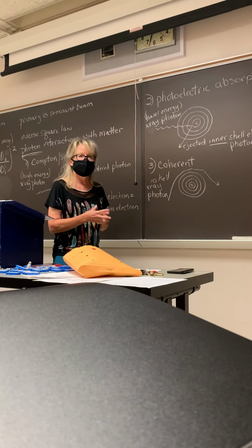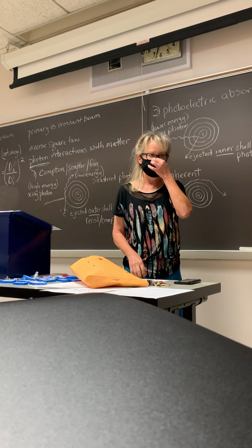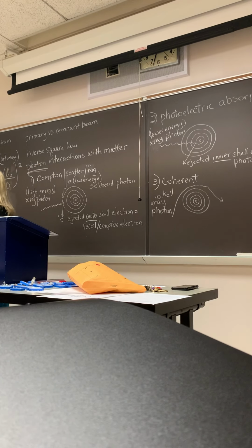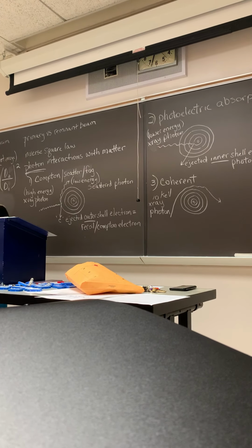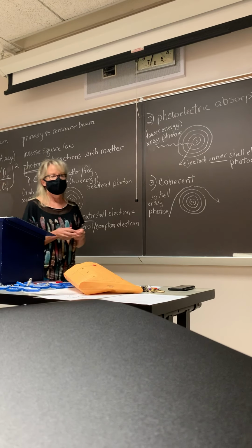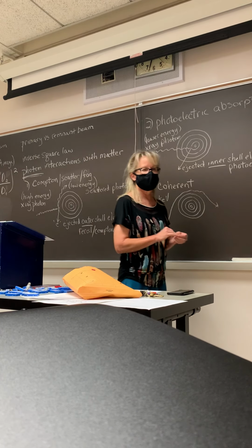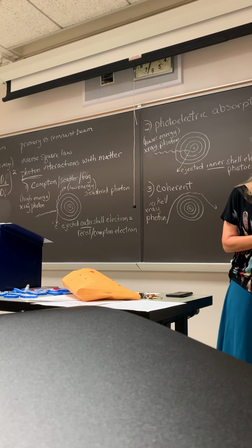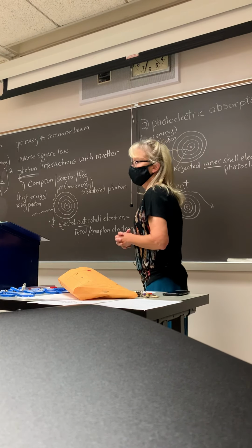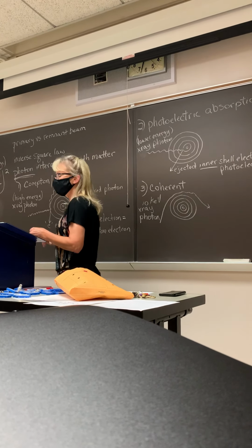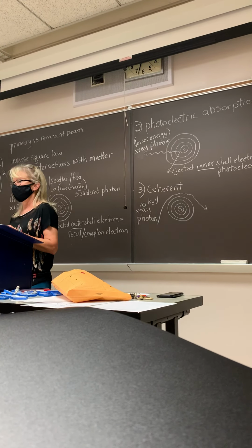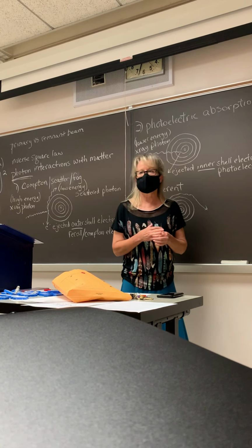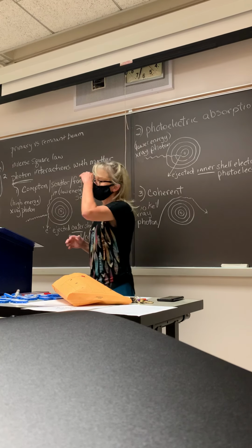Okay, next thing is HVL on your outline. What is HVL? Good, half value layer. So basically HVL is the thickness of the material. We're talking about filtration. The thickness of the filtration that will decrease the intensity of the beam to half the original. Half value layer.